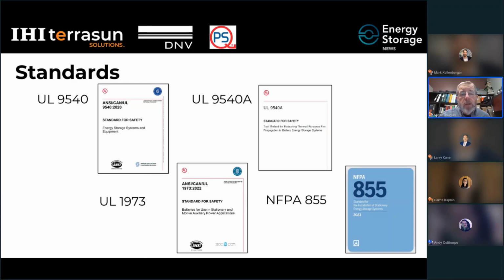When certification starts on these systems, it begins with the batteries, so it starts with UL 1973, then progresses to testing under UL 9540A. Once that's finished, UL 9540 is applied to confirm that the overall energy storage system meets its requirements.